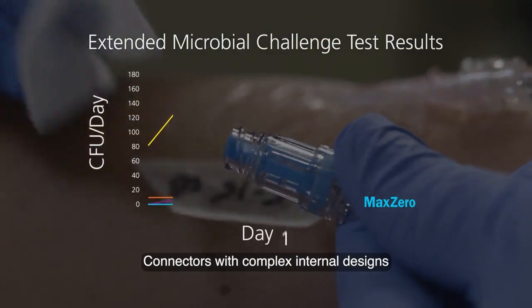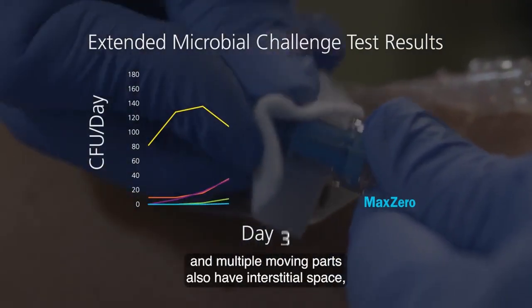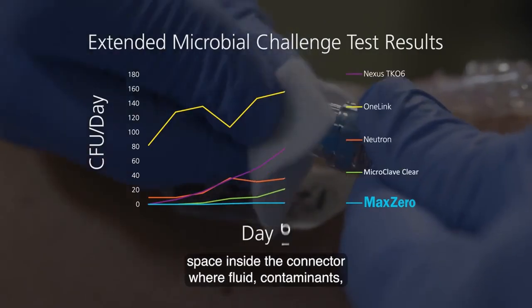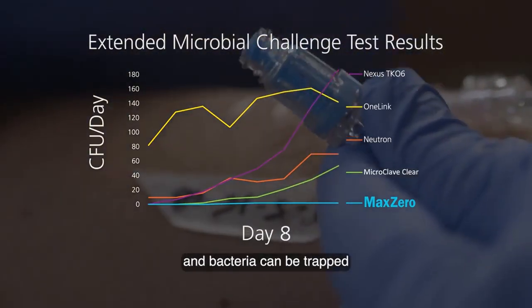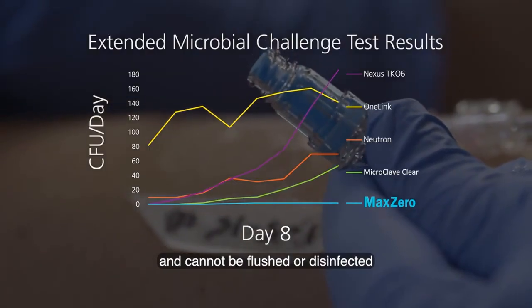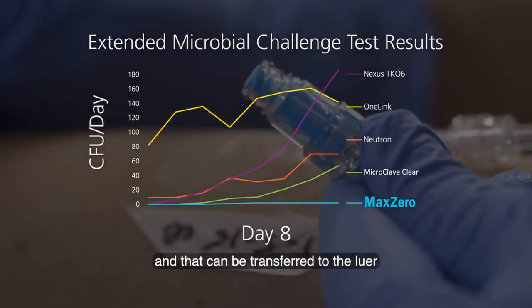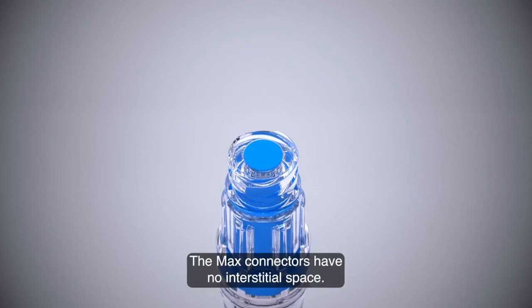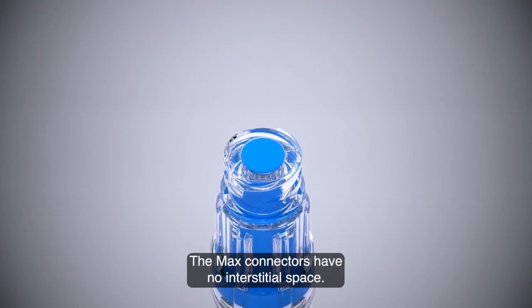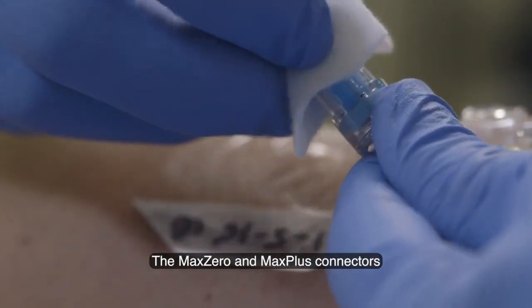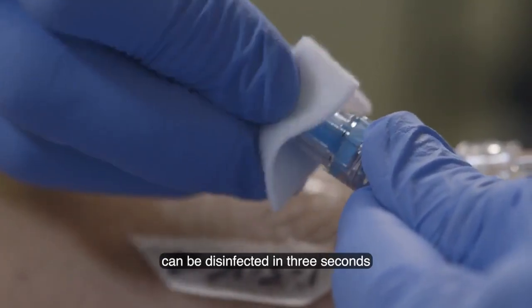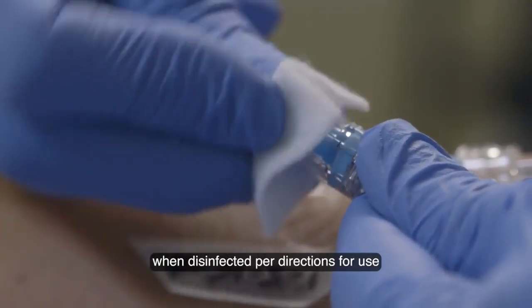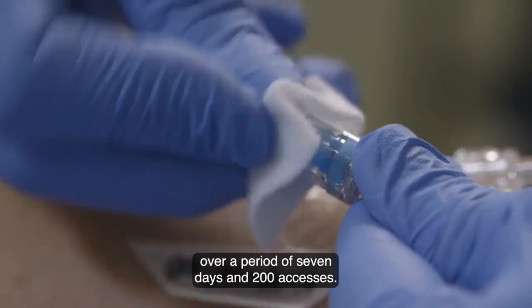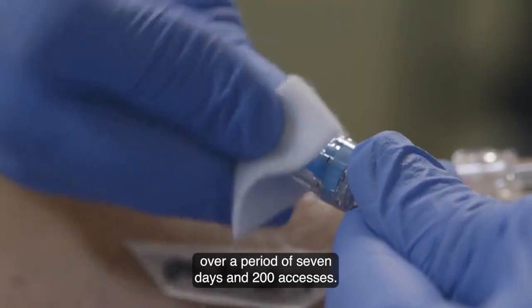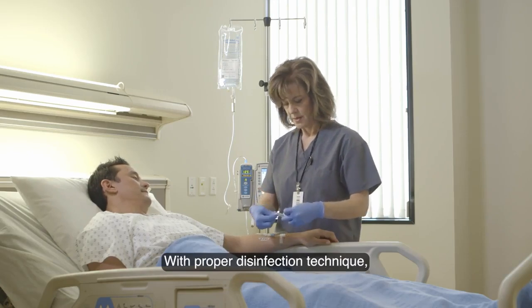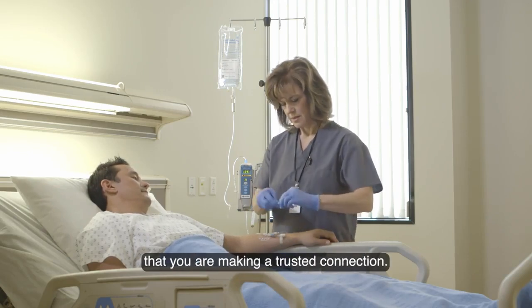Connectors with complex internal designs and multiple moving parts also have interstitial space inside the connector where fluid, contaminants, and bacteria can be trapped and cannot be flushed or disinfected, and that can be transferred to the luer and ultimately to the fluid path. The Max connectors have no interstitial space. The MaxZero and MaxPlus connectors can be disinfected in 3 seconds and maintain a microbial barrier when disinfected per directions for use over a period of 7 days and 200 accesses. With proper disinfection technique, you can be confident that you are making a trusted connection.